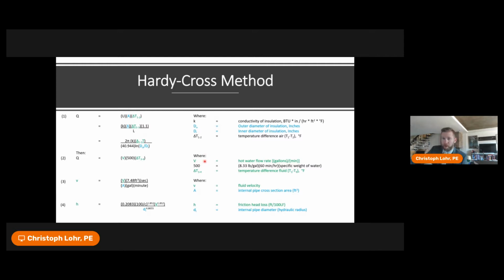So we have the flow rate itself that's needed to maintain that temperature. We have the temperature differential from the fluid as it goes into the hot water system and then comes out of the hot water return system. And then we also have our fluid velocity, which is a concern based on pipe material. And finally, our head loss. The head loss and flow rate are the two criteria that are the most key in sizing the pump.